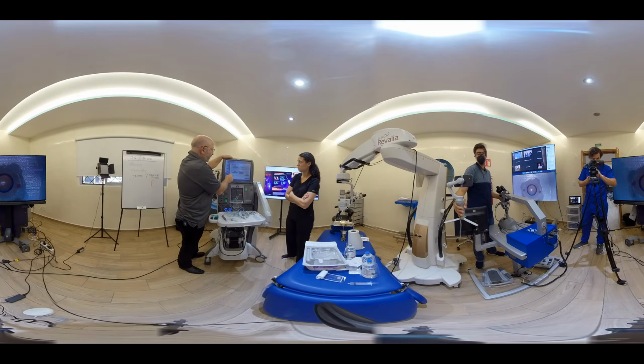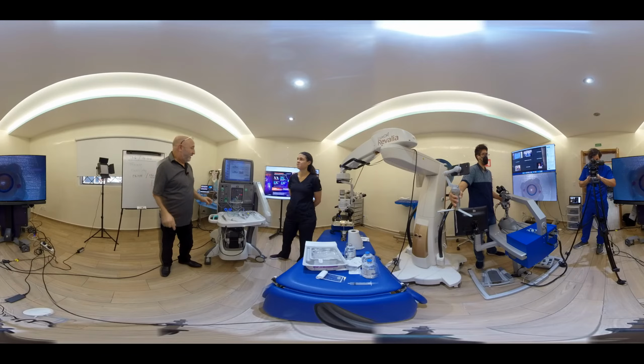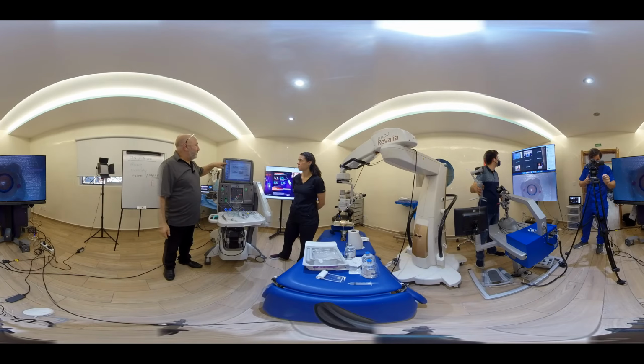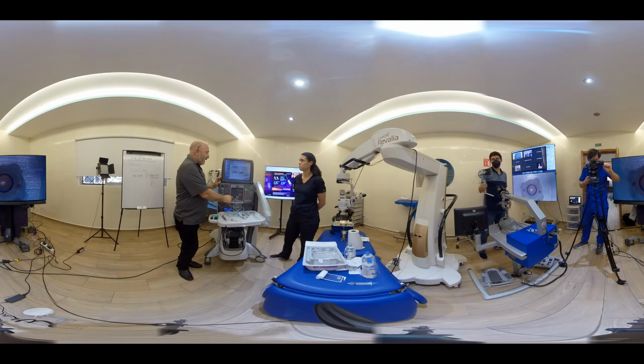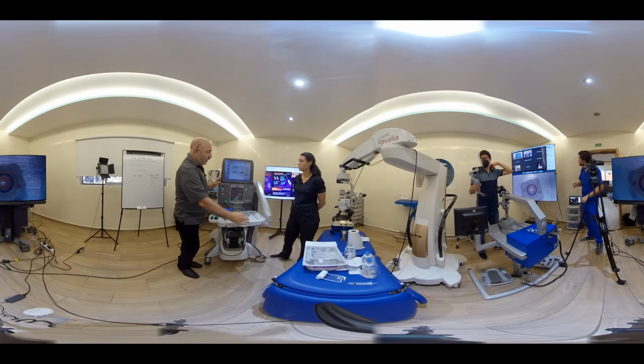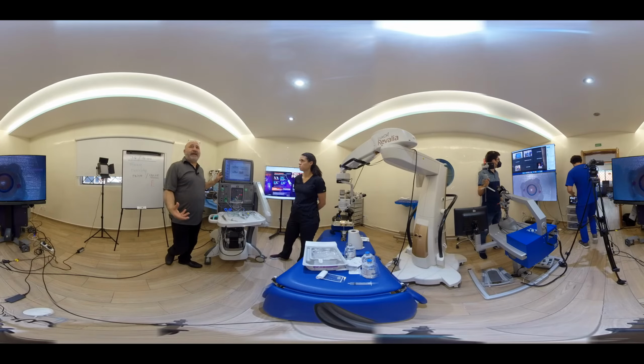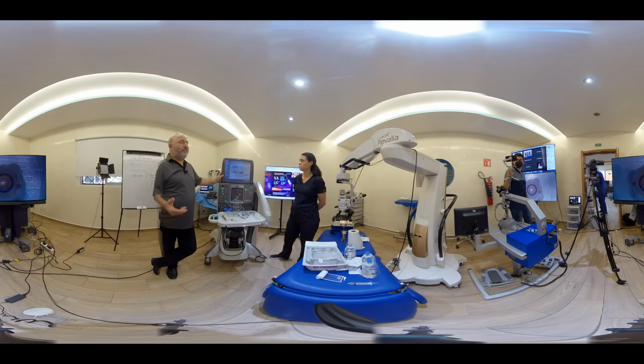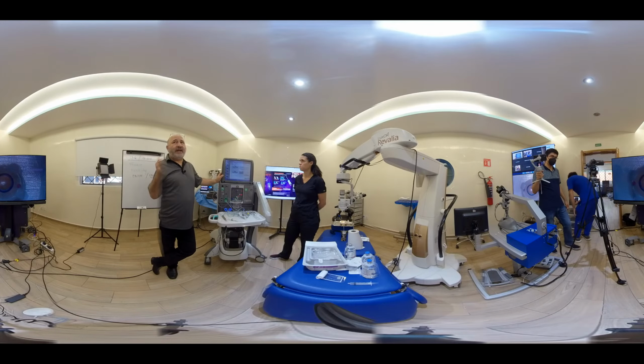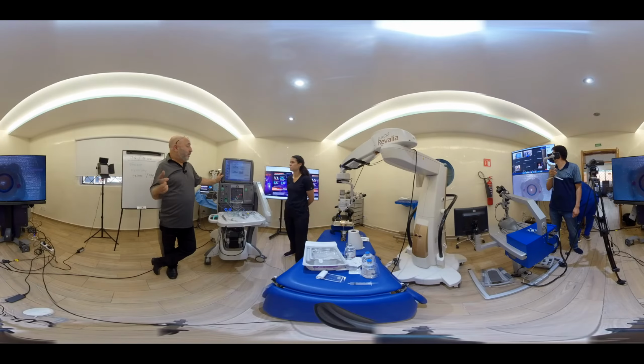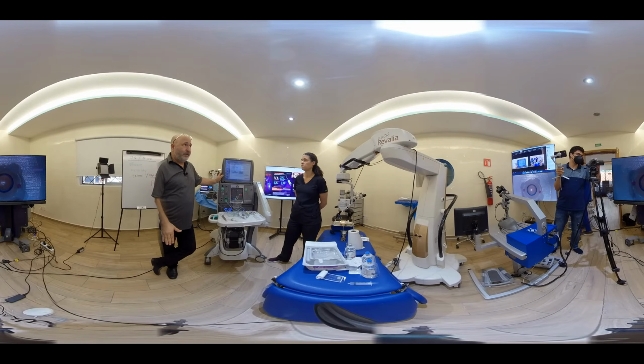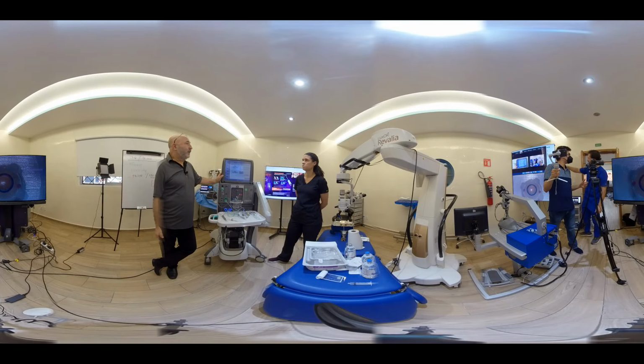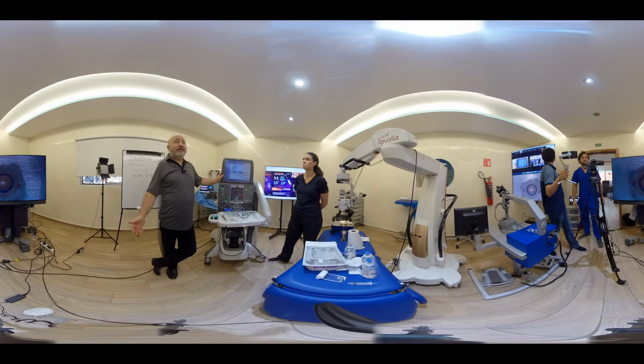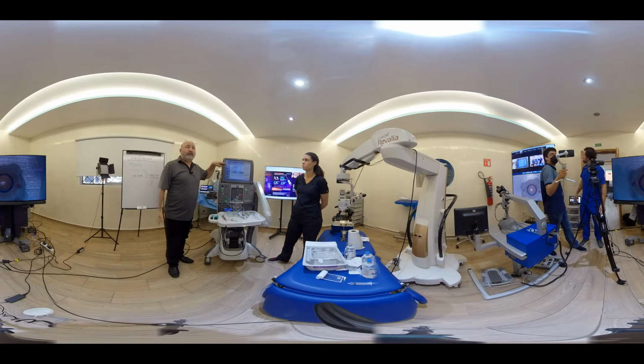The reason is a little thing called gravity. For you to get this 25 millimeters of mercury in the eye, the system assumes that the eye is at this level. Anything below that, you have to add the gravity effect. And the gravity effect is 1.86 millimeters per every inch that you're below. So if you're 10 inches below, and let's call it 2 millimeters for every inch, we'll round up, that's 20 millimeters more pressure than what it says here.